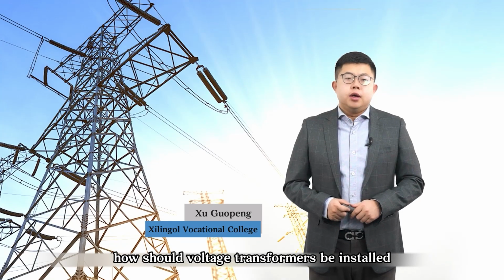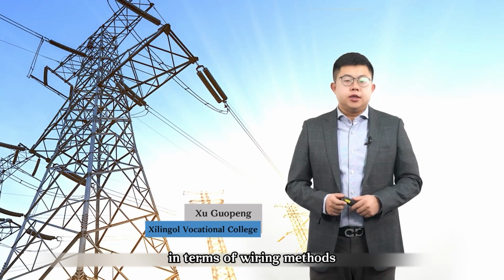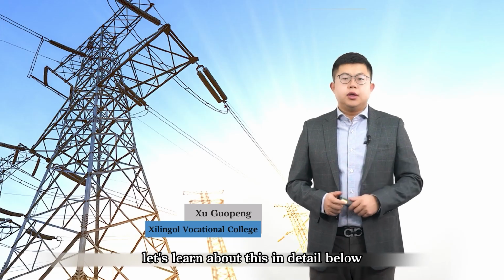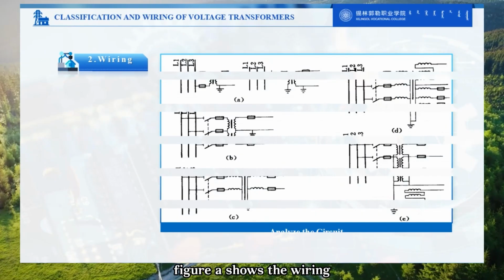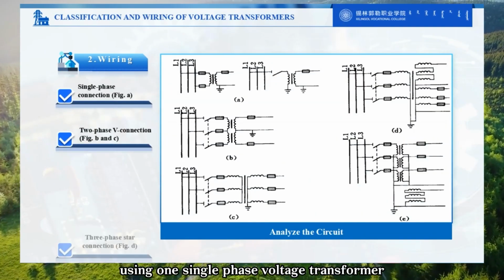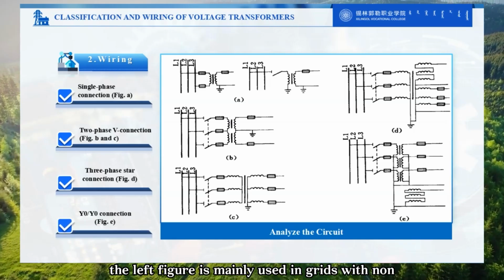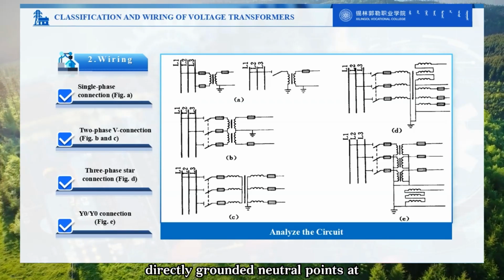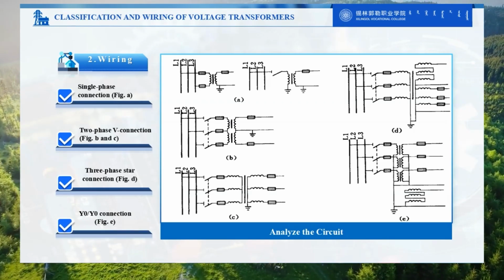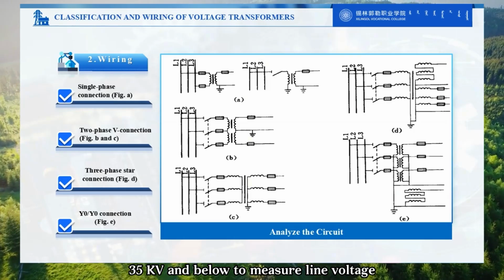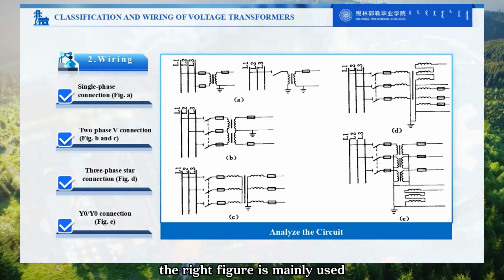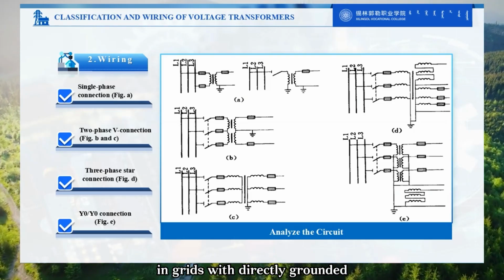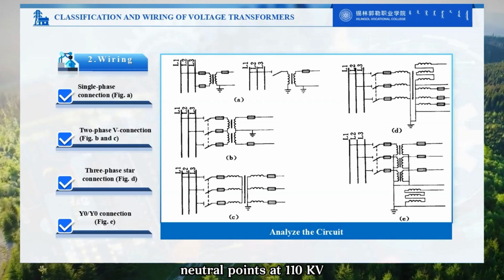How should voltage transformers be installed in terms of wiring methods? Let's learn about this in detail below. Figure shows the wiring using one single-phase voltage transformer. The left figure is mainly used in grids with non-directly grounded neutral points at 35 kV and below to measure line voltage.